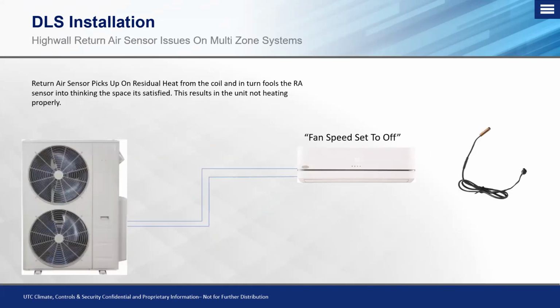Now, typically what we see is if we have a two-headed, three-headed, or four-headed system, we're going to shut these fan speeds off after set point, which is done by accessing the advanced service menu through our wireless remote controller. Okay, and on the high wall style units, we do that because of where that return air sensor is located. If you've ever serviced one of these units, if you pop open the front cover, and you take out the right side filters, you'll see there's a little plastic tab that slides right into the indoor coil fins. And inside of that is your return air sensor.